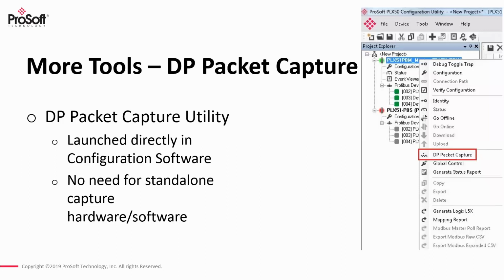And so like I mentioned before, if you had communication issues on your network, or you're having trouble getting a device up and running and into data exchange mode, a lot of times what you had to do is rely on third-party hardware, where you had to install either a tap on the PROFIBUS network, or tee off one of the existing PROFIBUS connectors, and then run another external software package to capture the PROFIBUS DP packets to get a clear indication of what really is going on within that bus.